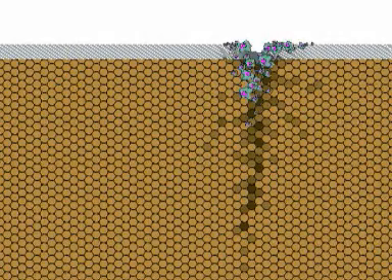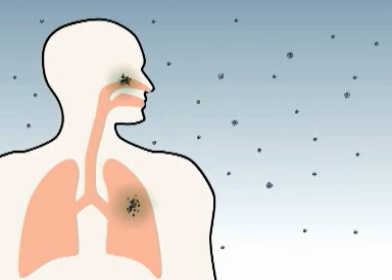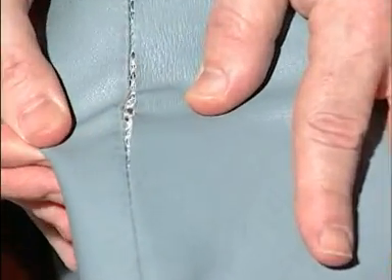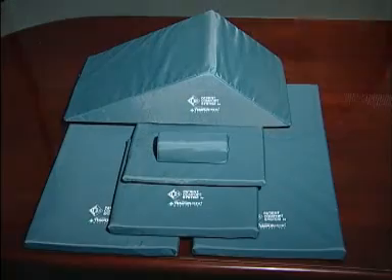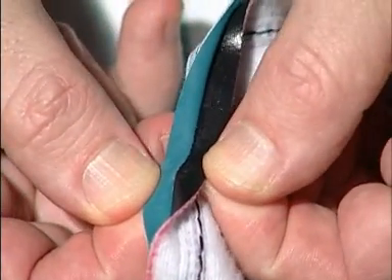Pads used in medical imaging are often frayed and torn. This is a great concern because it allows bacteria such as MRSA access to the central foam core, where it is impossible to clean. MRSA growing in this foam core can lead to direct patient contamination, and more concerning is recent research demonstrating the possibility of aerosolized spread of MRSA. This is why older pads need to be replaced with advanced pad systems that incorporate antimicrobials into both the foam core and the covering material, and have welded seams to stop bacteria from accessing the central core.